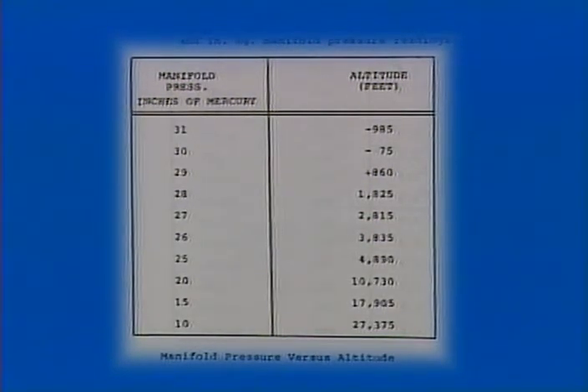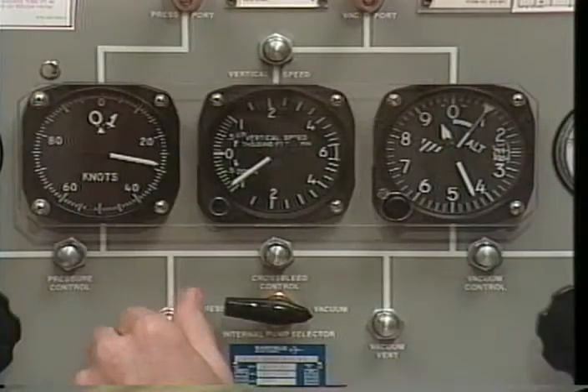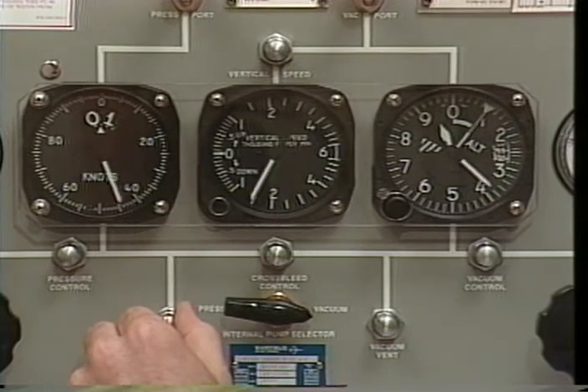For tests below field elevation, open the pressure control to simulate lower altitude. For test points above current altitude, open the vacuum control to achieve the higher altitude. Use these two steps to evaluate all the necessary test points. To end the test and return the system to ambient pressure, open the pressure vent.